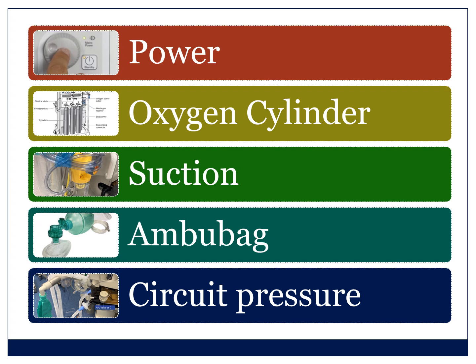So those are the things. If you're going to do nothing else, check the power, check the oxygen cylinder, the suction, that there's an ambu bag, check you can generate circuit pressure. And if you do that before every Caesar or spinal, you're a long way to having some sort of reassurance that your equipment's going to get you through the case.